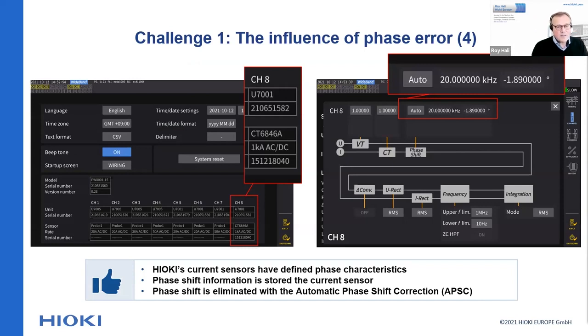Here you see two screenshots of the PW8001. Here on the left-hand side, you can see that the instrument has recognized a CT6846A current sensor, which has a range of 1000 amps for AC and DC. And this has a serial number, which is shown here at the bottom. At the same time, you can see here on the right that the instrument has set the phase shift correction automatically, meaning that the phase errors are being compensated for the full frequency bandwidth of the power measurement. We call this automatic phase shift correction, APS-C, and it's a plug-and-play solution, unique in the power measurement market of today.